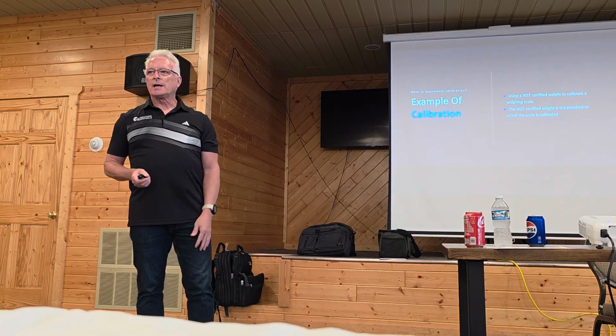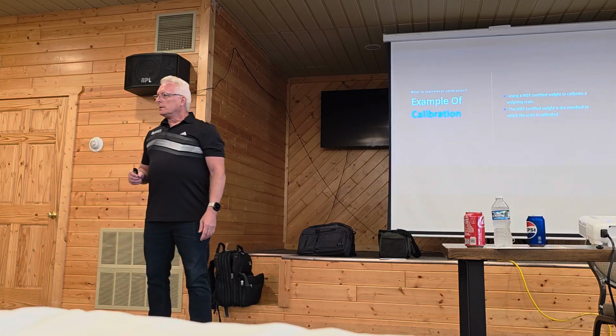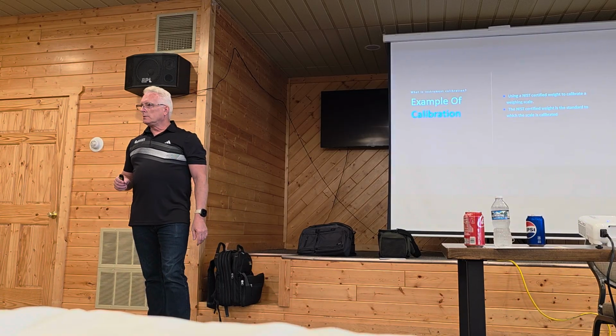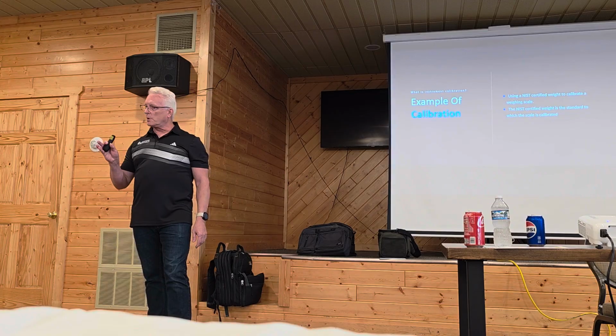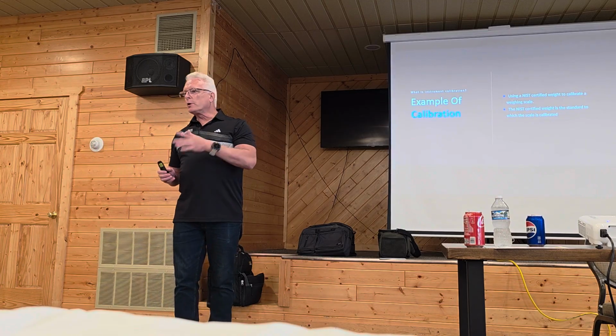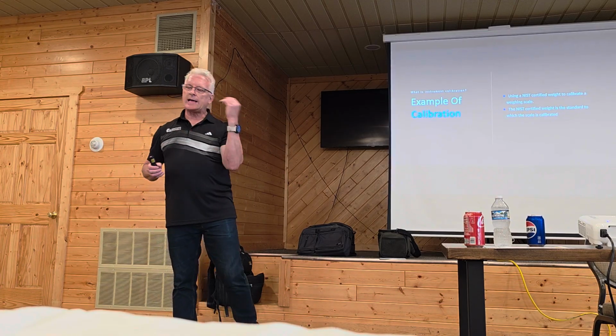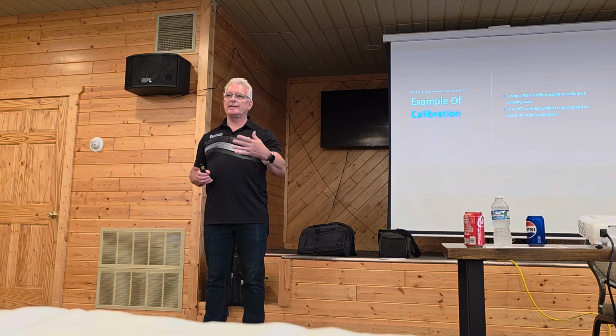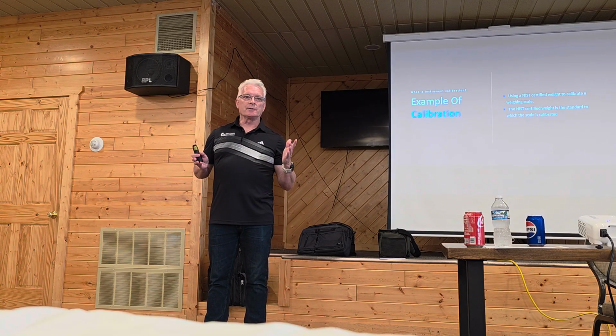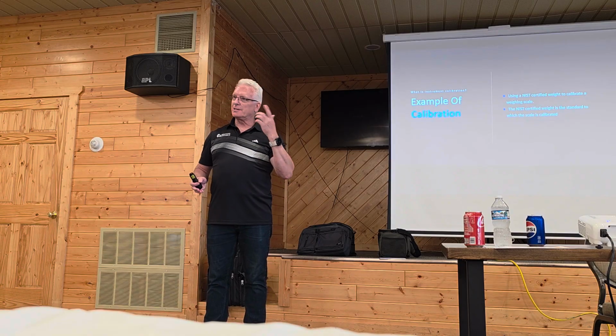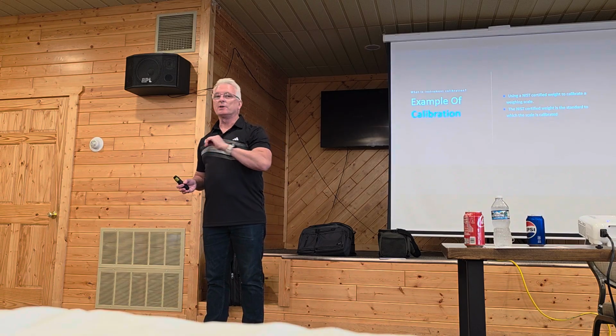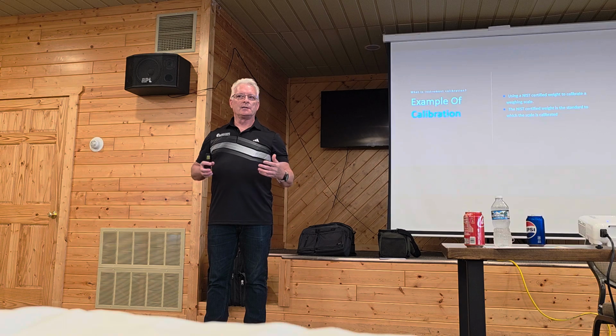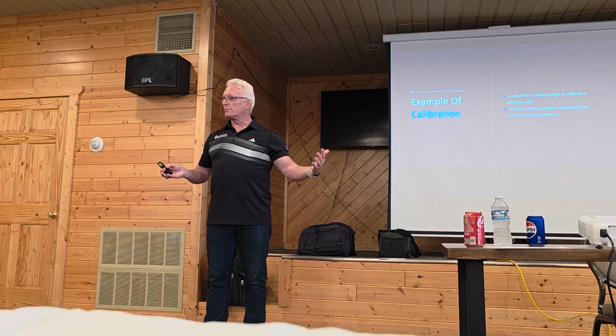So, are you calibrating with actual flow on the mag meters, or is it all in the software? So there's different ones. There's 3 or 4 different ways you can do calibration. Calibration is anytime you test something, even if you don't make an adjustment, they consider it a calibration. I used to think anytime you did it, it had to be adjusted to be a calibration, but it doesn't necessarily have to be adjusted. You still performed it and you checked it and you made sure it was correct.